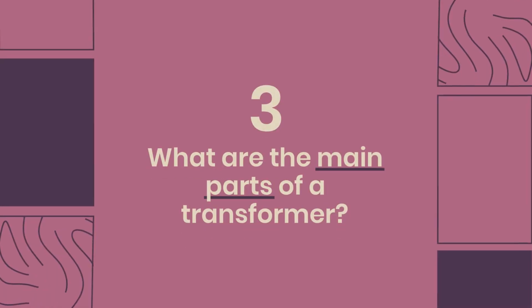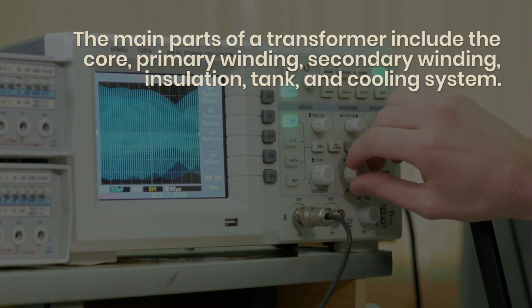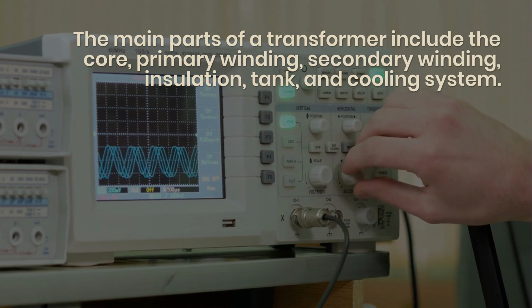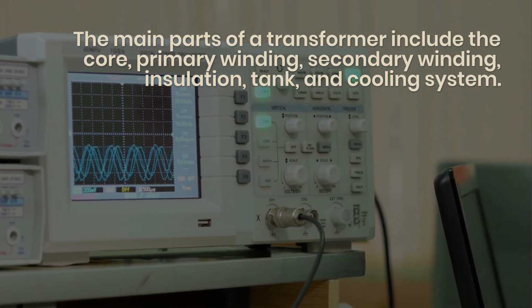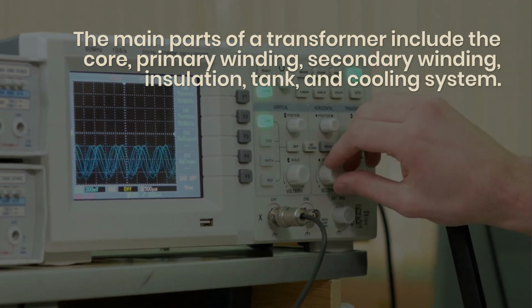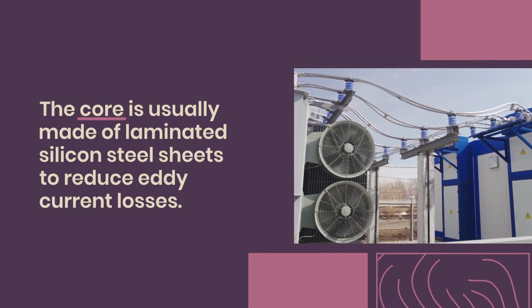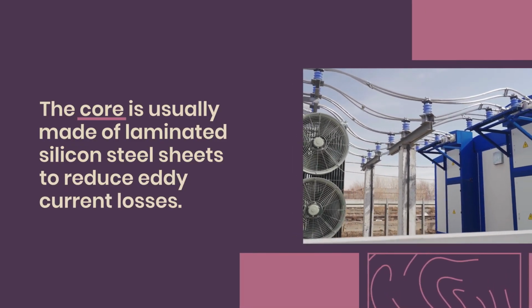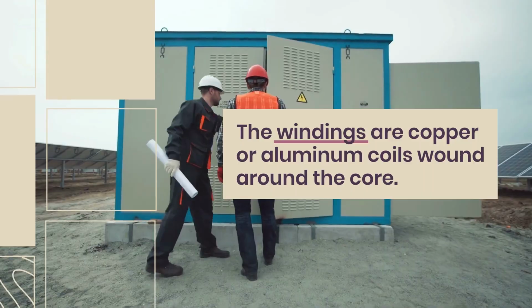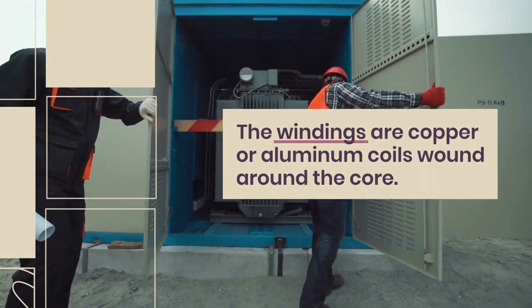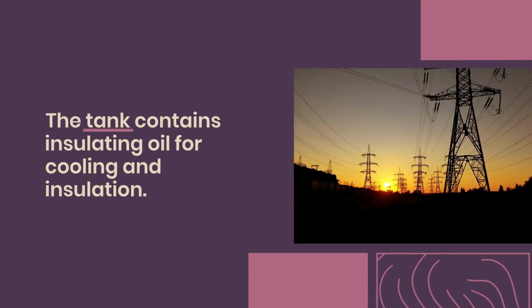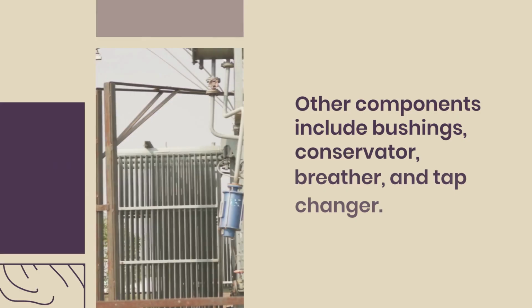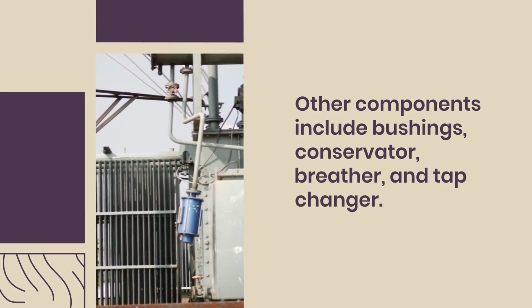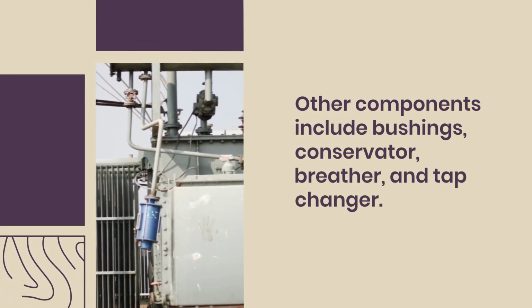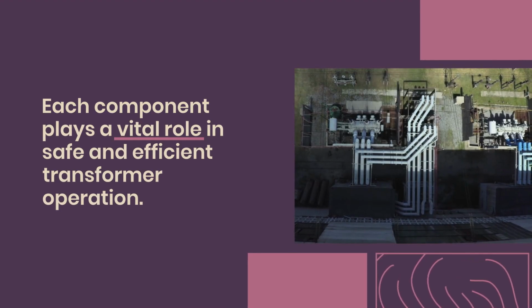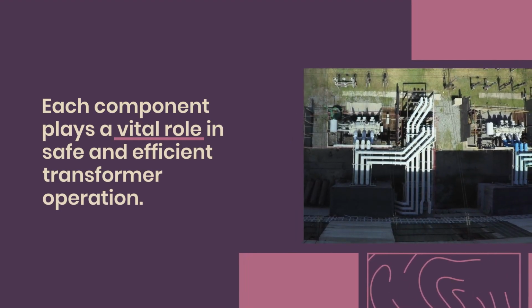3. What are the main parts of a transformer? The main parts of a transformer include the core, primary winding, secondary winding, insulation, tank, and cooling system. The core is usually made of laminated silicon steel sheets to reduce eddy current losses. The windings are copper or aluminum coils wound around the core. The tank contains insulating oil for cooling and insulation. Other components include bushings, conservator, breather, and tap changer. Each component plays a vital role in safe and efficient transformer operation.